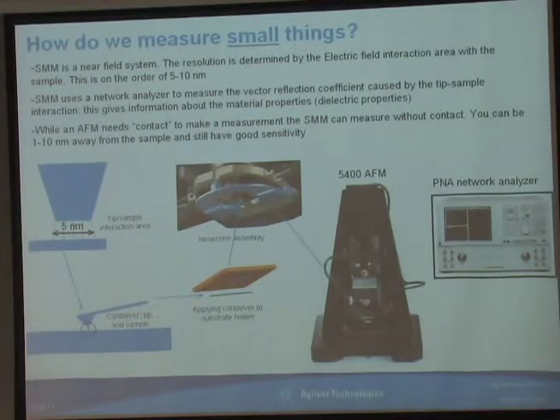Just for the others of you, an AFM is like an old record player needle, it's a stylus. You have a very precision X and Y scanner that drags or bounces the stylus over a surface. The stylus is at the end of a cantilever, and you bounce a laser off the cantilever, look at the fringes of the laser interference pattern, and can measure the vertical position of the cantilever to angstroms. So what you're actually doing is a topographic map of a surface where you know where you are in X and Y, and you're measuring Z to create a topographic map of a surface.